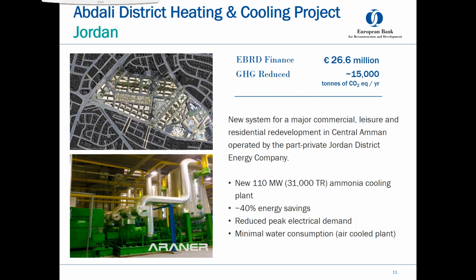So the project had some very positive environmental impacts, and for the technical people listening, I can give you a little bit of detail. It was based upon ammonia chiller plant, and at the time that it was built, I believe it had the largest thermal store for a district cooling plant, which was 80,000 cubic meters in size. The idea, which would be very familiar to those people involved in the district cooling space, is that the thermal store allowed most of the cooling demand to be met by being generated at nighttime and stored for use during the day. This had a positive impact on peak electrical demand, and there were also some special characteristics that minimized water consumption. And Amman is a particularly water-stressed area.